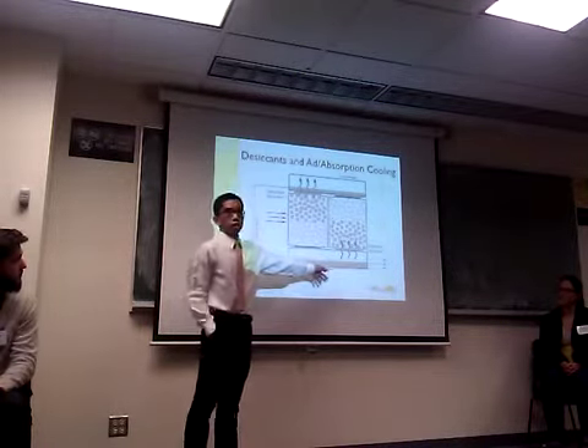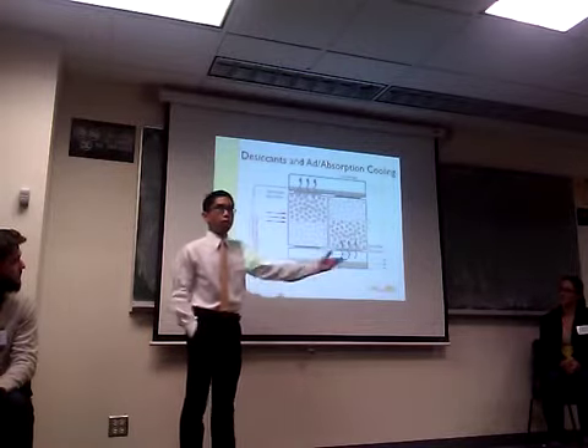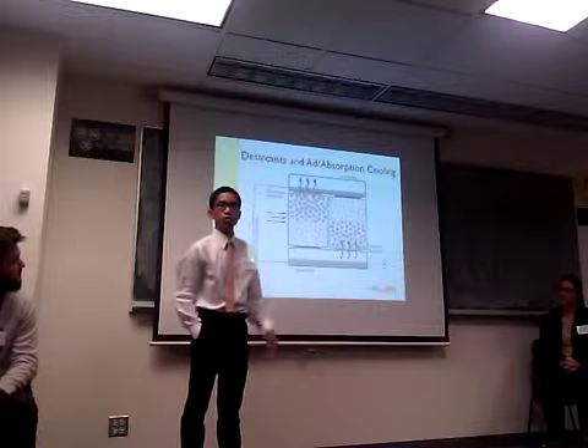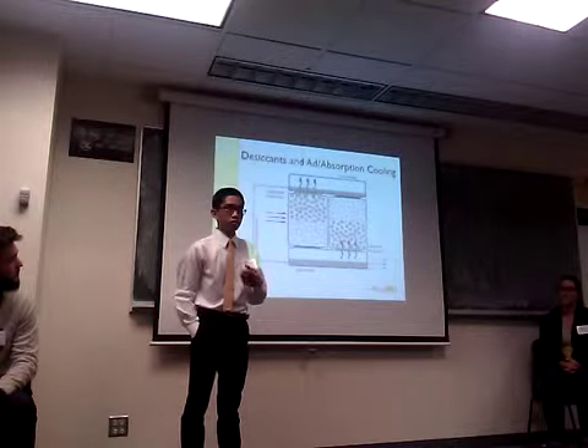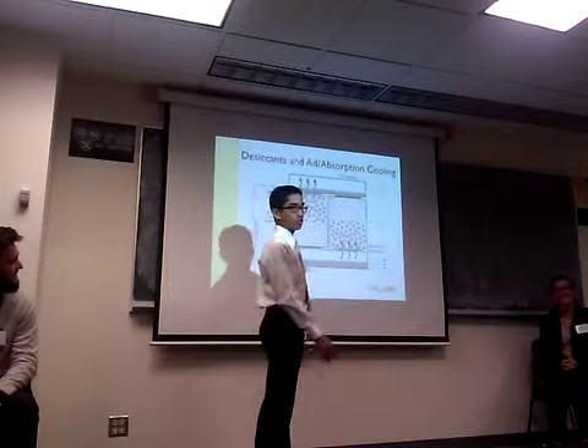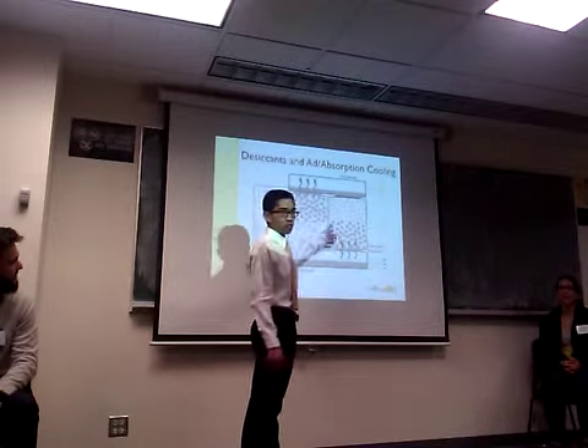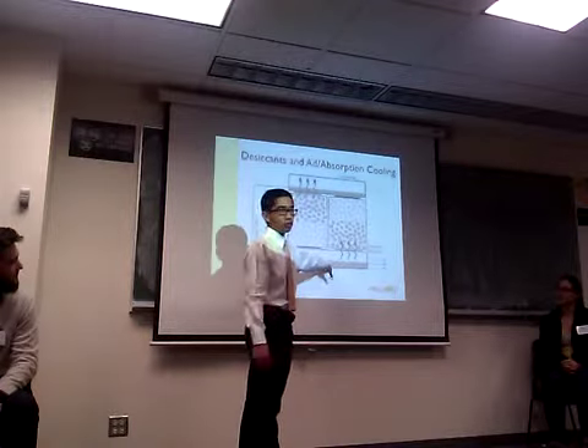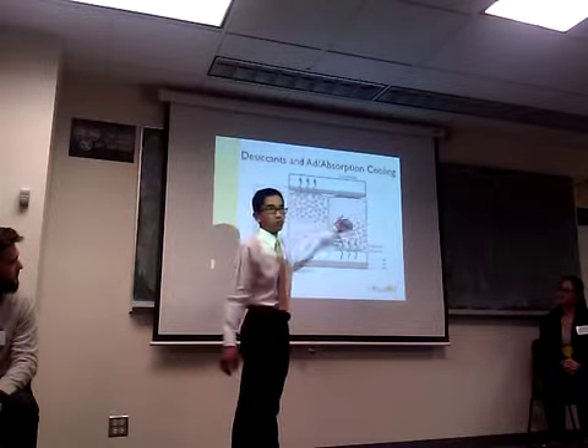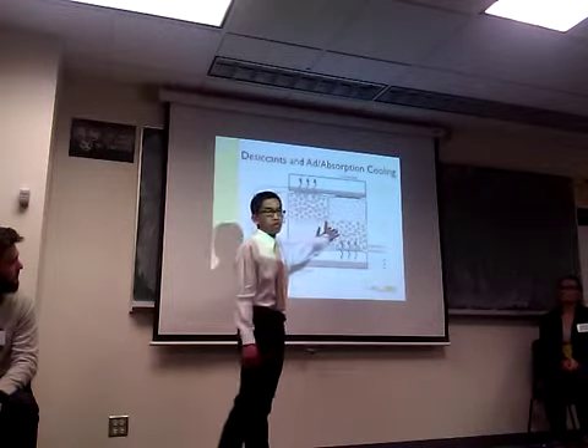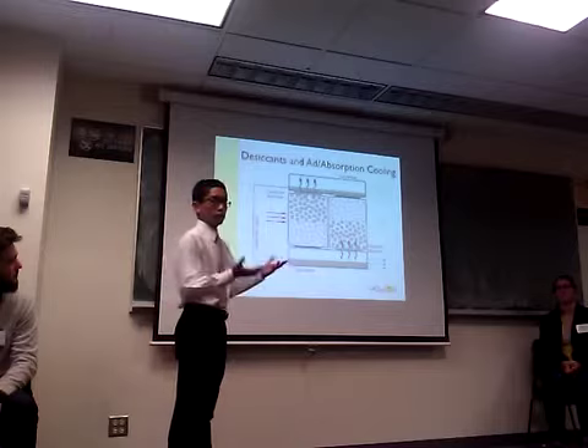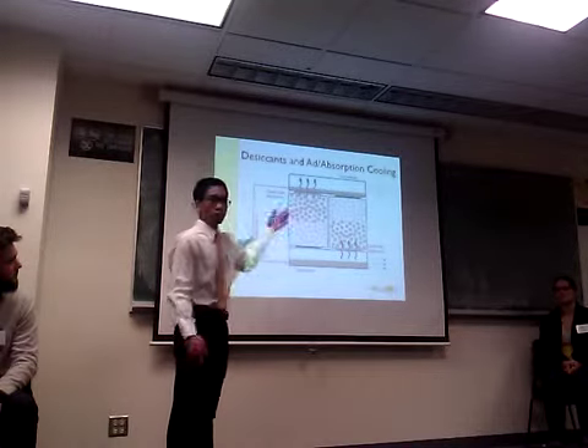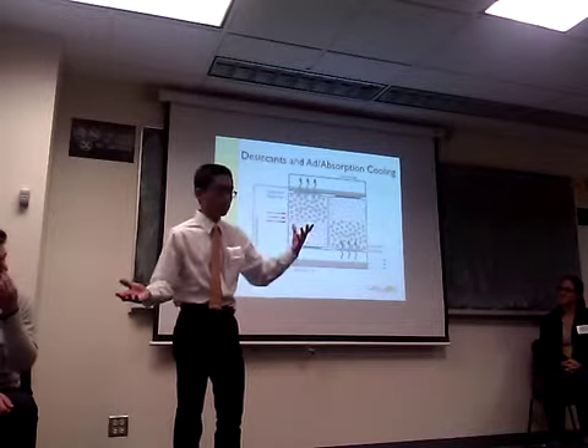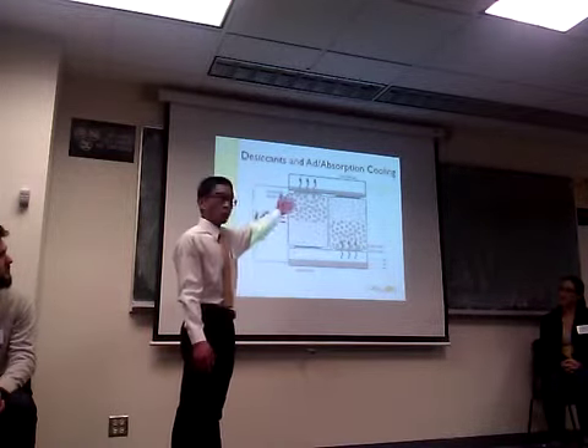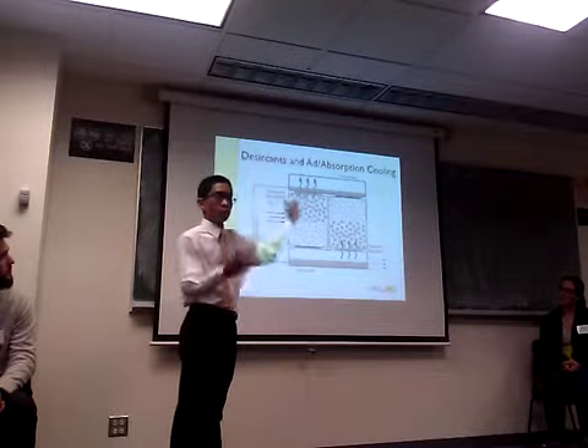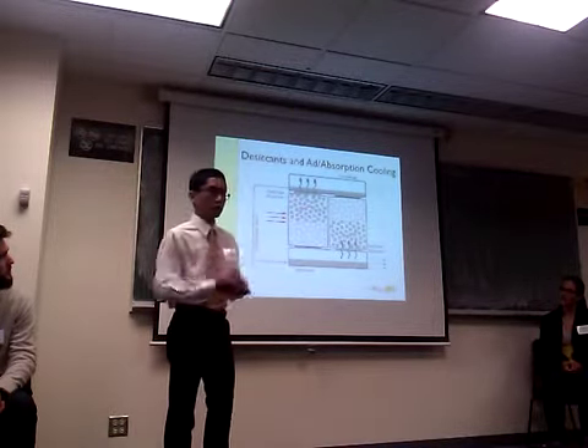This would be at a low partial pressure or in a vacuum, and what happens to a liquid when it's at a low pressure and gets heat? It evaporates. That water vapor, usually water, will go into the desiccant. I know this shows two chambers, but to simplify, once it's absorbed in the desiccant, to renew it so it can continue to absorb water and heat from the room, we'll use the energy collected from our solar collectors to drive the water vapor off the desiccant so that it can be renewed, dry again, to collect more water.